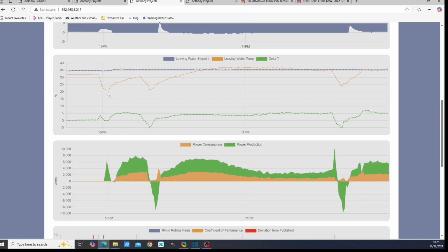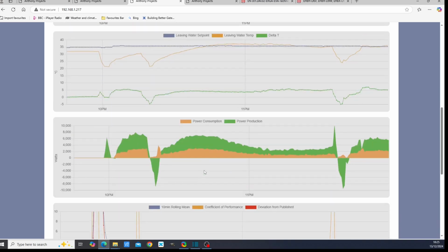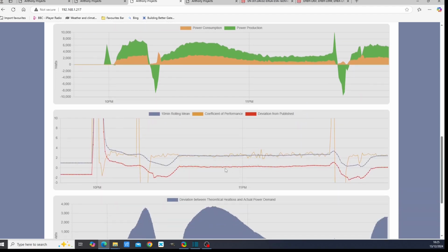The reason it was using the compressor was because the temperature of your leaving water never dropped below 18 degrees in this particular example. So that's good, but you can see there's quite a lot of energy which is being put in here, and this is compensating for the fact that the heat pump was switched off for the previous 3 hours. And all told, we can see in this regime here, we've got a coefficient of performance of about 2.4. That's not bad for a cold winter's night, minus 5.5.